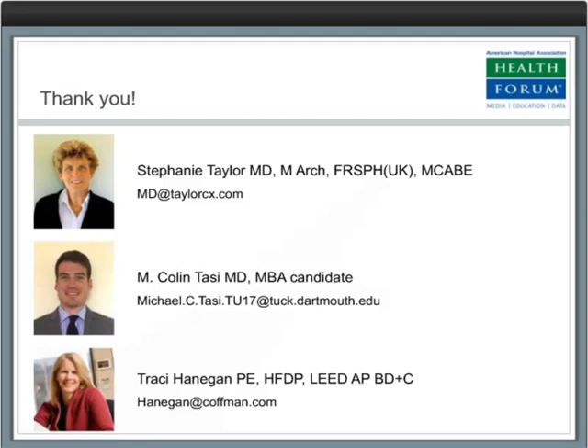Ms. Hannigan? Yes, I have heard stories of humidification systems causing it to rain in operating rooms and all kinds of scenarios. When I dig down deeper, I find that oftentimes there was something going on with the control of the system or the installation. I remember a call about a project where it was raining in the hallway outside an operating room because the humidification system had supposedly saturated the duct and it was pouring out. Ultimately what was found is that the duct was dry, that someone had accidentally punctured part of the humidification canister up in the air handler, and that it was leaking out. Yet the story gets told and the myth goes on that there was rain in the ductwork. But control is a big issue, getting control loops tuned and understanding that these humidification ranges are also very temperature dependent.